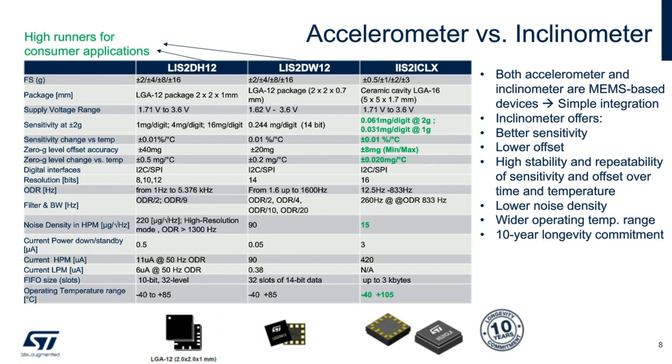The inclinometer offers better sensitivity, lower offset, high stability and repeatability of sensitivity and offset over time and temperature. It has much lower noise density — only 15 µg per square root of hertz versus 90 and 220. And it has a temperature range from minus 40 to plus 105 degrees Celsius. Because of these improvements, a much more accurate tilt angle can be achieved using the IIS2ICLX.